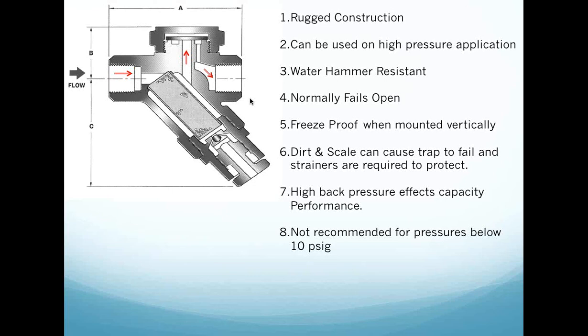A thermodynamic disc trap uses the properties of steam and condensate, and in this regard, the sensible heat in that condensate. So it manipulates that condensate as it flows across that body. It moves through an orifice, so it takes a pressure drop. And as it takes a pressure drop, that liquid flashes at that lower pressure, and that becomes the motive force to snap that disc back down on its seat and hold. So we end up using the property of that sensible heat in that liquid as we move across the orifice and take a pressure drop. The sensible heat cannot be retained in the liquid itself, and so a percentage or portion of it flashes. That becomes the actuator that snaps that disc down. It's very simple. It works really well.